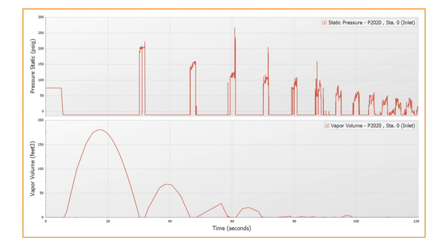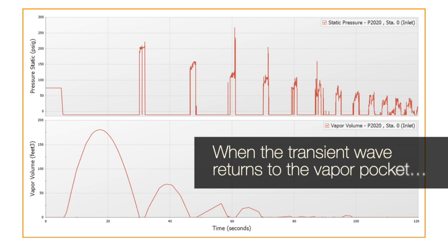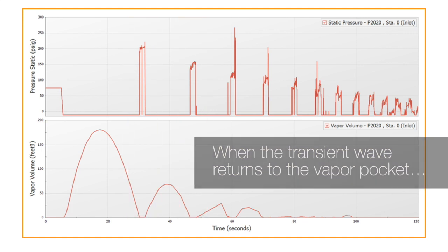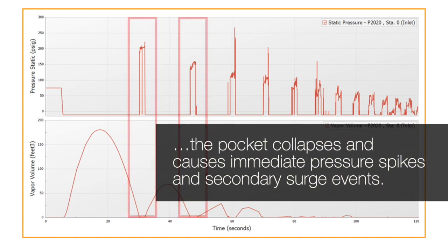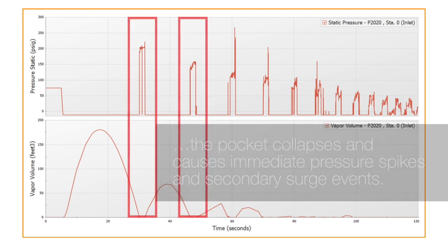Surge models show a growing vapor cavity as the pressure drops below the fluid's vapor pressure and into full vacuum. When the transient wave returns to the vapor pocket, the pocket collapses leading to immediate pressure spikes and secondary surge events.